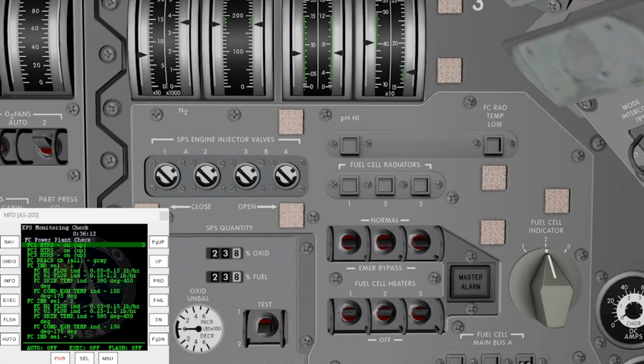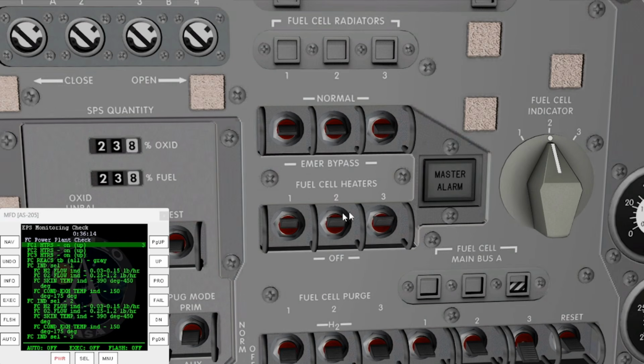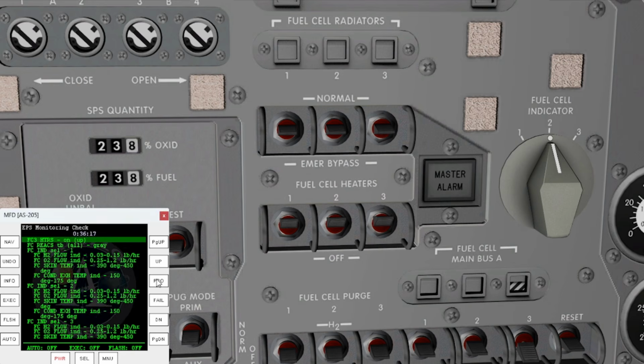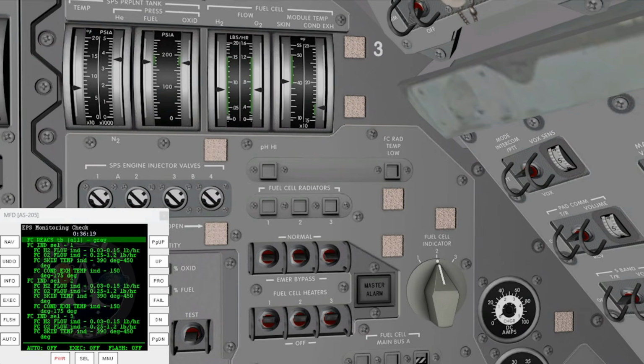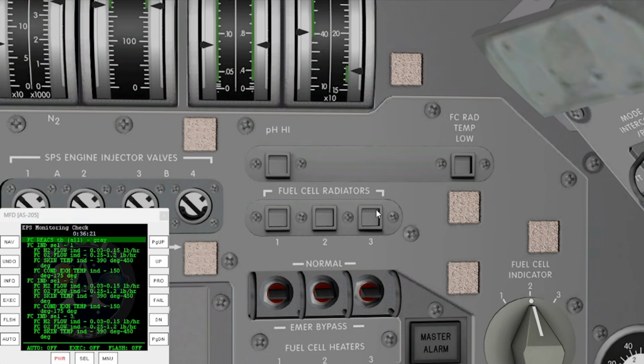Fuel cell power plant check will make sure each of the inline heaters are on. Fuel cell REACS talkbacks are all gray. So that's pH high. pH is a measure of acidity. If it's high, it'll go barber pole. If it's standard, it'll go gray. You want it to be on gray.